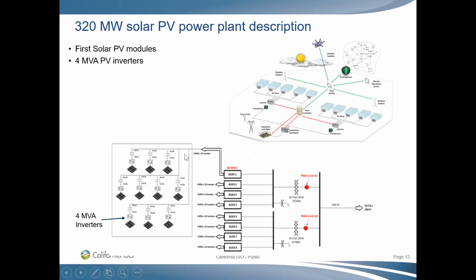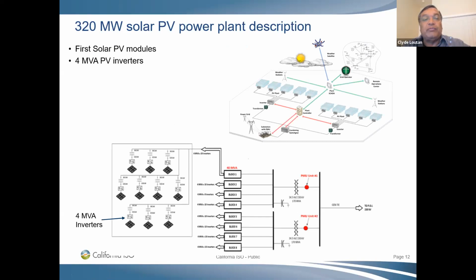So this plot here shows you the first test that we did. It was a 320 megawatt solar PV plant. The footprint of this solar PV plant is on the lower or bottom part of this slide. Each one of those inverters is a 4 MVA, and then you've got 10 inverters making up one block. Then you've got 8 blocks. And the beauty of this is each inverter can operate independently.